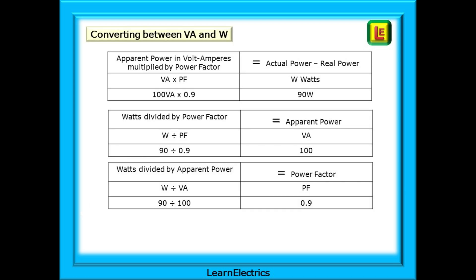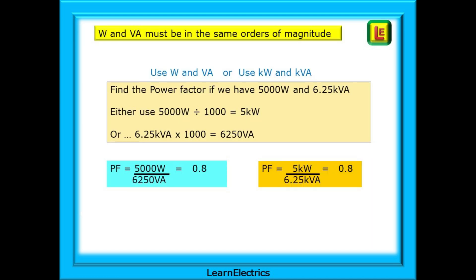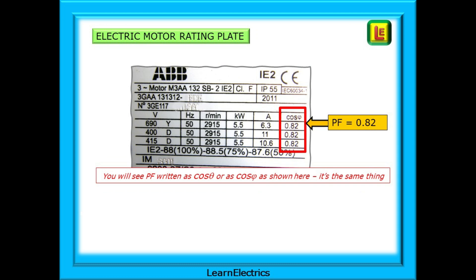This comparison chart should help — pause the video and study it. If we know any two values of VA, PF or W, we can always find the third. When doing calculations, W and VA must be in the same orders of magnitude — use watts and volt amperes, or kilowatts and kilovolt amperes. For example: 5000 watts and 6.25 kVA — convert 5000 watts to 5 kilowatts, or convert 6.25 kVA to 6250 VA. Either way, the answer is a power factor of 0.8.